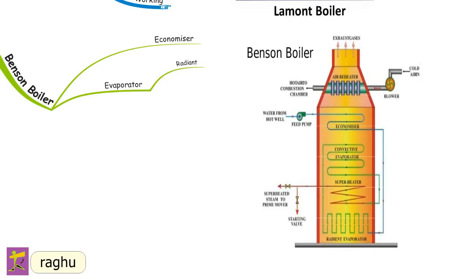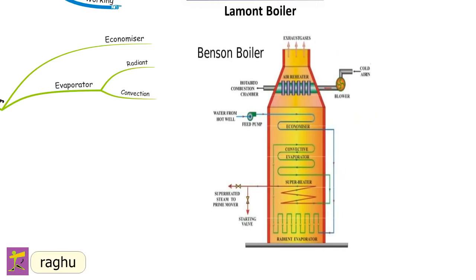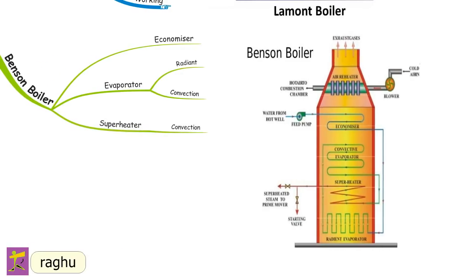In the radiant evaporator, water is partly converted into steam by receiving heat from fuel through radiation. The remaining water from the radiant evaporator is evaporated in the convection evaporator, where heat is absorbed from hot gases by convection, producing saturated high-pressure steam at 210 kgf/cm². The saturated steam is then superheated in the convection superheater, and the superheated steam is supplied to the steam turbine.